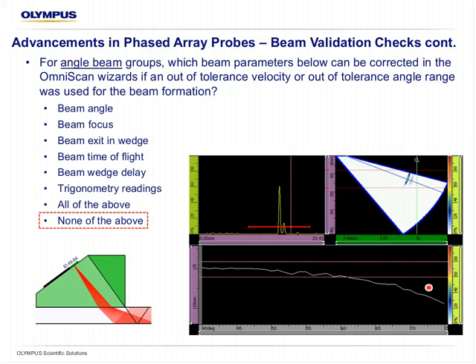And in this scenario, we can see that the focal laws between 40 to approximately 60 degrees are valid and very tight within the tolerance, but the higher angles here are out of tolerance. Okay, the velocity of the material, the excessive beam angle steering outside its range will all have an effect on that, in addition to the actual wedge wear.